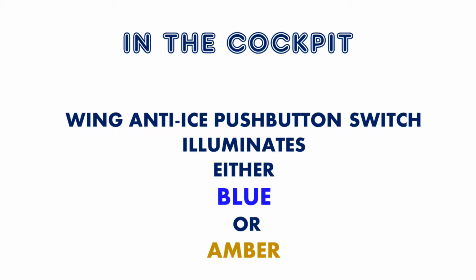So when does the fault light come on? What's going to trigger it to show on the display? There are different reasons: the left or right valve just fails to open, or the changeover relay doesn't operate, or a fault relay. Any of your relays that don't work, the fault light's going to come on. Also, if the left or right valve air outlet pressure is too low, or the valve fails to open or close, or relays aren't working right - those are all good reasons why the fault light comes on.